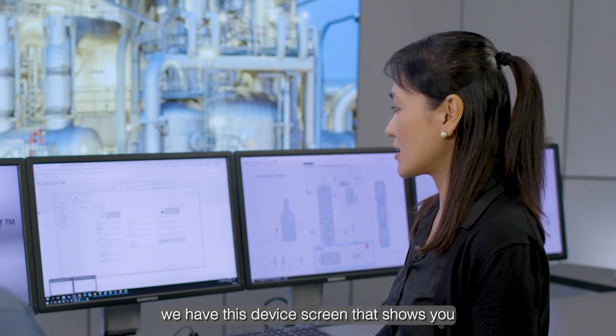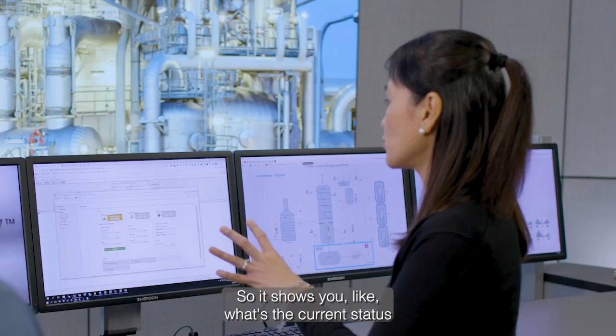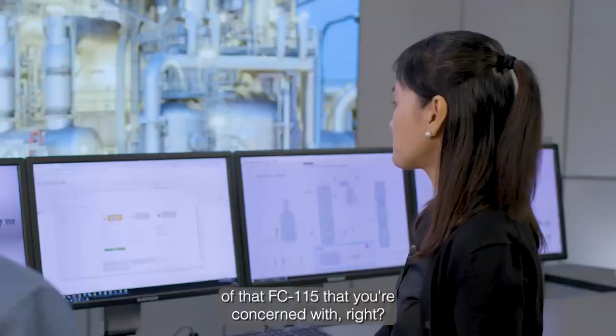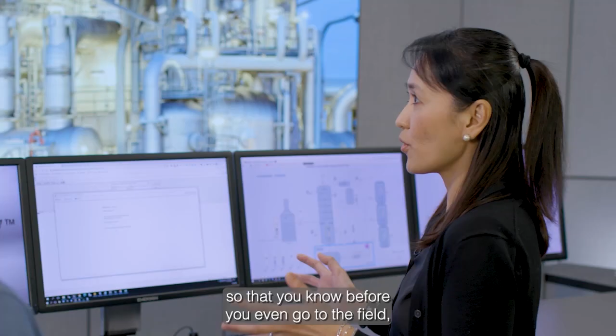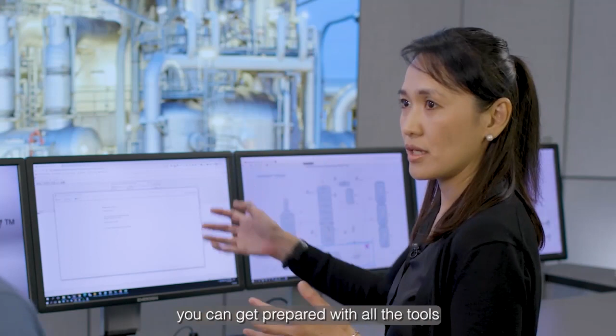I was showing you earlier that we have this device screen that shows all the configuration parameters for FC115. Now I'll go to the overview page, and this shows that there's an alert for this device. It shows the current status of the FC115 you're concerned with. Depending on the information available on the device, it will tell you why there's a maintenance alert, and also provide recommended actions, so before you even go to the field you can get prepared with all the tools you need to fix the issue.